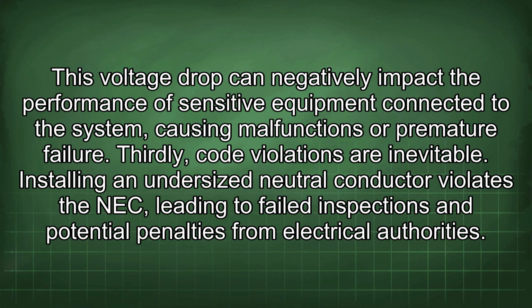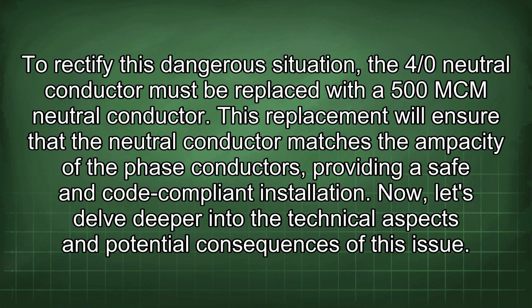Thirdly, code violations are inevitable. Installing an undersized neutral conductor violates the NEC, leading to failed inspections and potential penalties from electrical authorities. To rectify this dangerous situation, the 4/0 neutral conductor must be replaced with a 500 MCM neutral conductor. This replacement will ensure that the neutral conductor matches the ampacity of the phase conductors, providing a safe and code-compliant installation. Now let's delve deeper into the technical aspects and potential consequences of this issue.